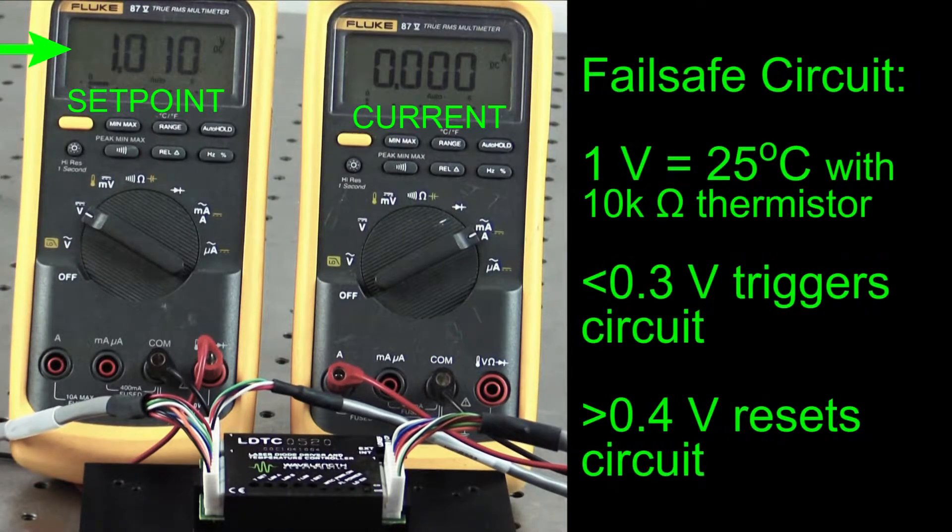The fail-safe circuit will reset the temperature set point to 1 volt if the temperature set point signal falls below 0.3 volts. This corresponds to 25 degrees C when using a 10 kilo-ohm thermistor. A set point greater than 0.4 volts resets the fail-safe circuit.